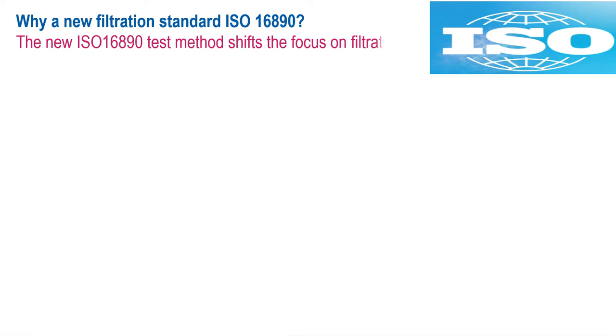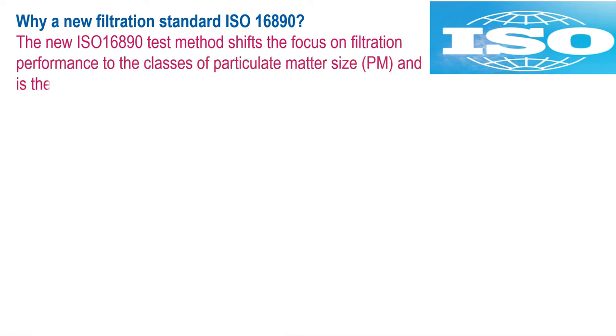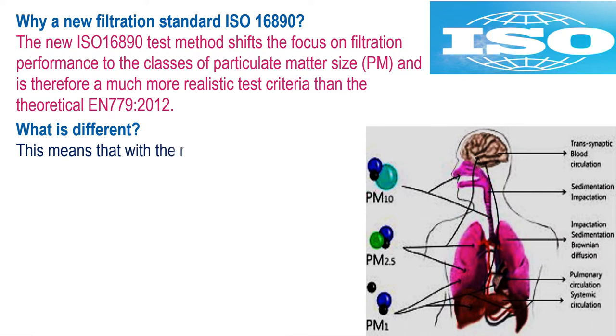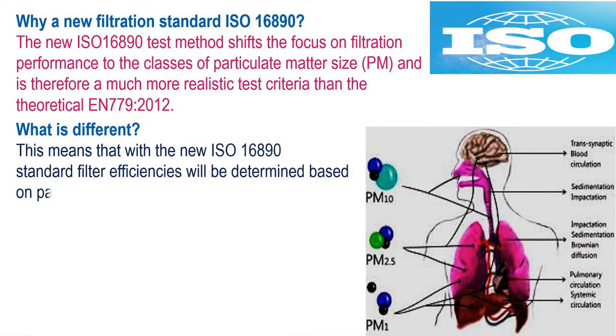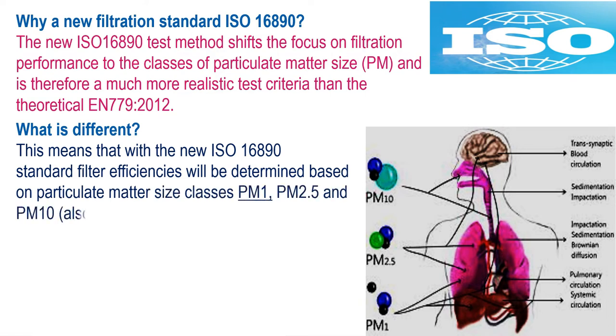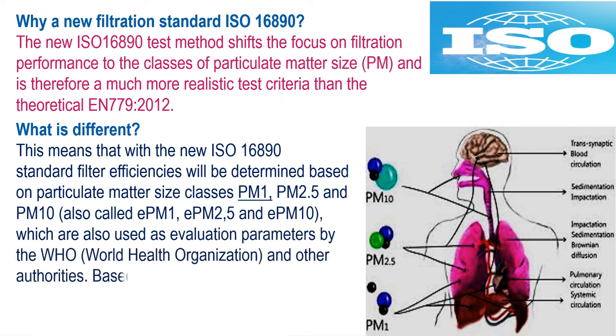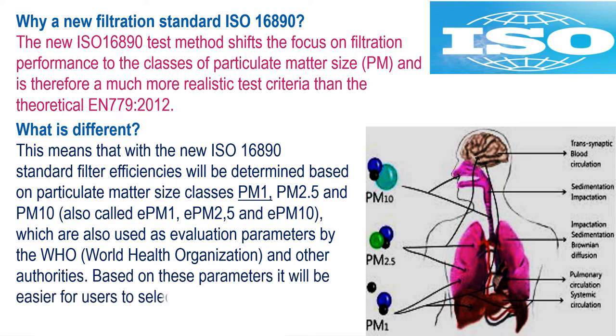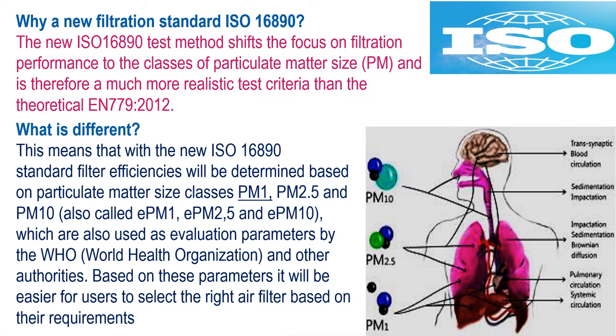Why a new filtration standard — ISO 16890? The new ISO 16890 test method shifts the focus on filtration performance to the classes of particulate matter size, and is therefore a much more realistic test criteria than the theoretical EN 779 2012. With the new ISO 16890 standard, filter efficiencies will be determined based on particulate matter size classes PM1, PM2.5, and PM10, also called ePM1, ePM2.5, and ePM10, which are also used as evaluation parameters by the World Health Organization and other authorities. Based on these parameters, it will be easier for users to select the right air filter based on their requirements.